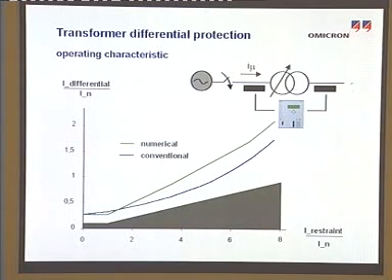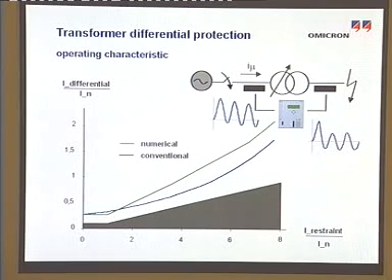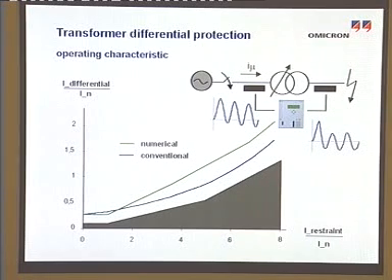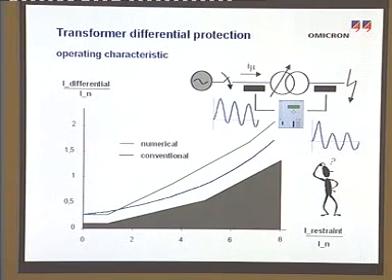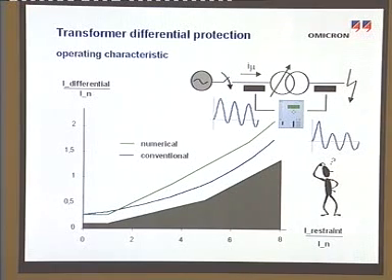In case of heavy through faults, the impact of CT saturation is taken into account by increasing the rise of the characteristic. While the effect of the first two differential currents can be calculated easily, the setting in the area of high stabilizing currents is difficult due to the non-sinusoidal behavior. Therefore, it is mainly based on experience. Many numerical relays are nowadays supplied with additional saturation detectors.